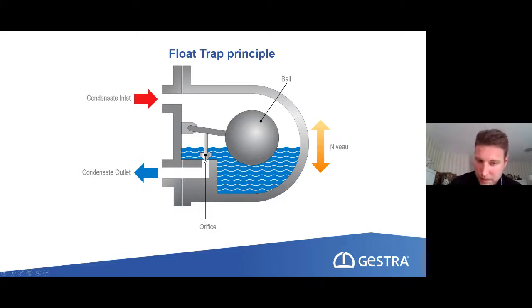It's a very simple principle, and here we have a first very big advantage of this kind of design, because we have the plug and the seat in the water area. This is one of the best things to guarantee that we don't lose any live steam, because this is something that is known as a water lock. So very similar to what we have in our bathroom. This kind of siphon that we usually have is also some kind of water lock that we need to guarantee that we don't get any gases from the canalization in our bathroom. And here the principle is, let's say, similar. As soon as we have a water level, steam cannot travel through it. But this is only, let's say, a principle.